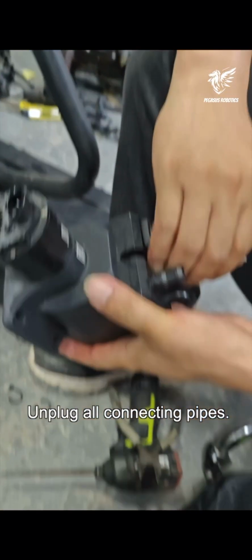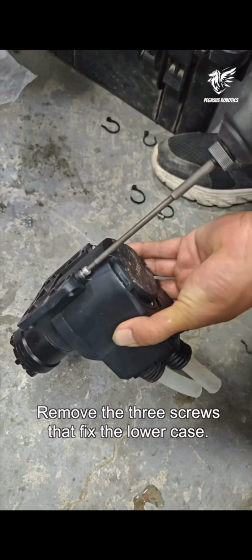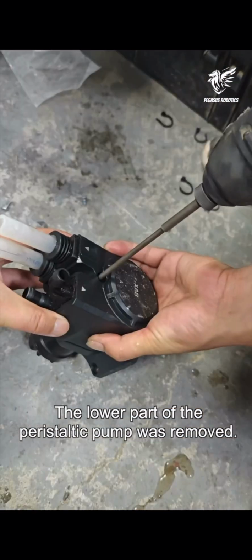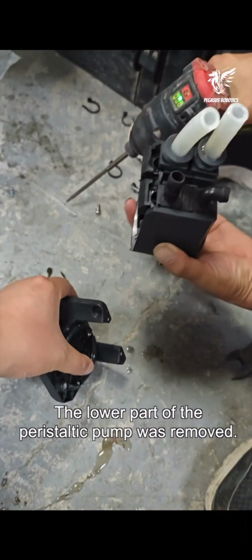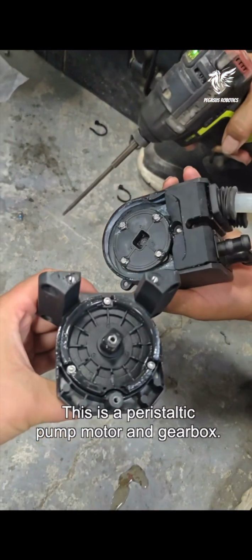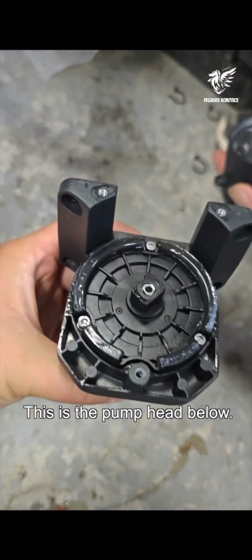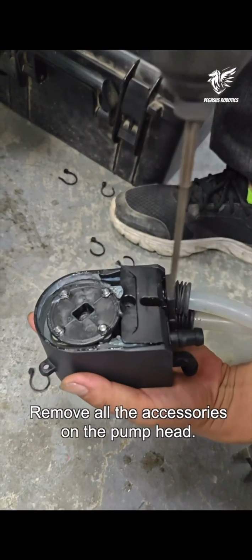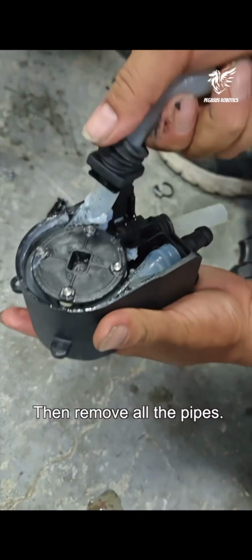Unplug all connecting pipes. Remove the 3 screws that fix the lower case. The lower part of the peristaltic pump was removed. This is a peristaltic pump motor and gearbox. This is the pump head below. Remove all the accessories on the pump head. Then remove all the pipes.